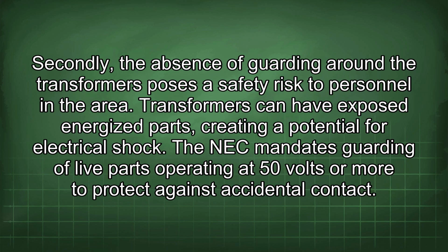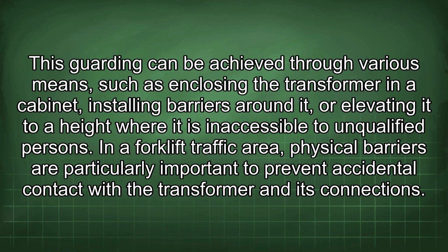Secondly, the absence of guarding around the transformers poses a safety risk to personnel in the area. Transformers can have exposed energized parts, creating a potential for electrical shock. The NEC mandates guarding of live parts operating at 50 volts or more to protect against accidental contact. This guarding can be achieved through various means, such as enclosing the transformer in a cabinet, installing barriers around it, or elevating it to a height where it is inaccessible to unqualified persons. In a forklift traffic area, physical barriers are particularly important to prevent accidental contact with the transformer and its connections.